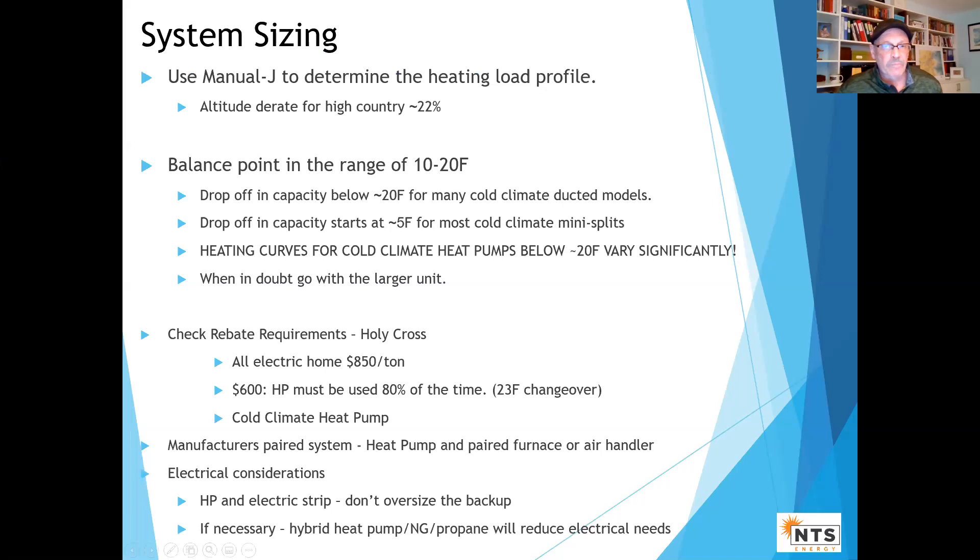The next few slides cover some design and installation thoughts. Manual J — derate for altitude. A couple of things about heat pumps: there's a drop-off in capacity, even though they're much better than they used to be, especially at about five degrees for mini splits. The heating curve for cold climate heat pumps has different drop-offs depending on the brand. So you want to be very cognizant of that when designing. When in doubt, go with the larger unit — typically a half ton or a ton up.